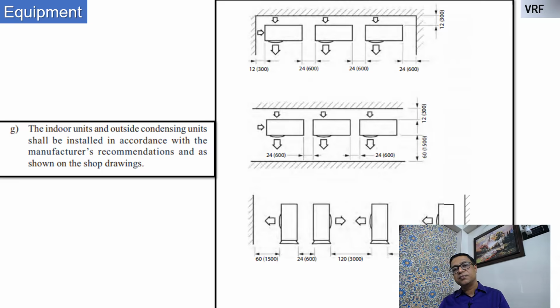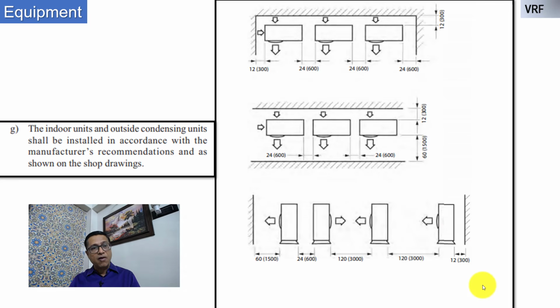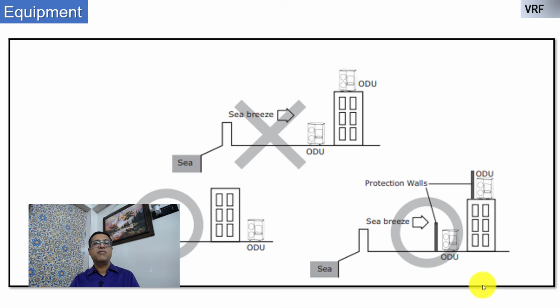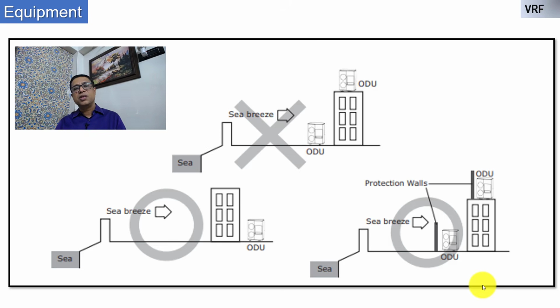These are some of the pipings. These are some of the guidelines, and they have to be taken from the OEMs, as these are general guidelines. How we can install the multiple units, what should be the distance from behind the walls, from the side walls, and between the units is given here. You can see all the possible location issues are identified here, but it is very important to get the manufacturer's recommendation for this. When you install the units near the sea, and the sea breeze becomes an issue, then you cannot install the unit like this. You can see in the top picture, the installation has to be either this or this.